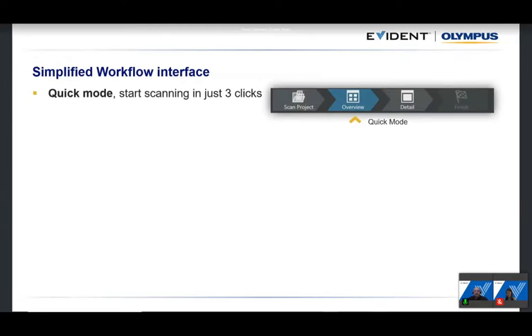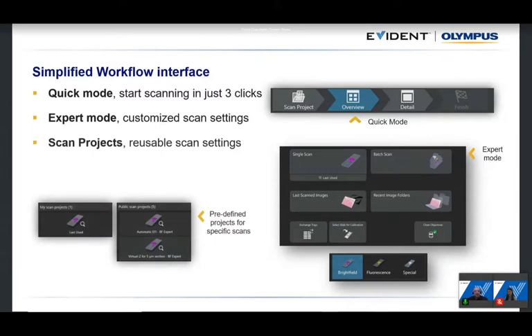The instrument supports different levels of users. A beginner can load a slide and start a scan in just three clicks, while an expert mode allows full control over every parameter. You can also save scan projects — for example a virtual Z-stack for a five-micron section — so that studies requiring extensive scanning always use consistent parameters, avoiding biases from changing settings mid-study.